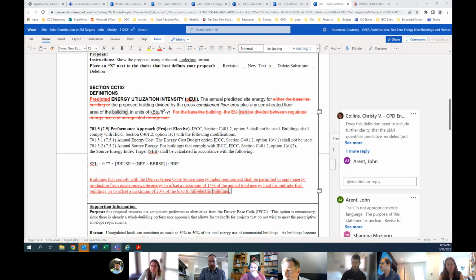It's just not feasible to hit these numbers without PV. If you've got to get 23% of your regulated loads, that's going to be more than 15% of your building. In a really high efficiency building, it's going to be 30% of your energy costs. So you're talking about a very large percentage of loads where you can't claim any savings, and the only other way to get savings from them is on-site renewables.